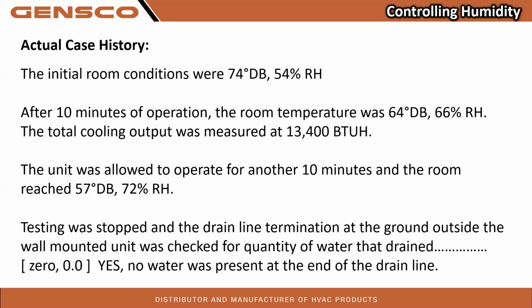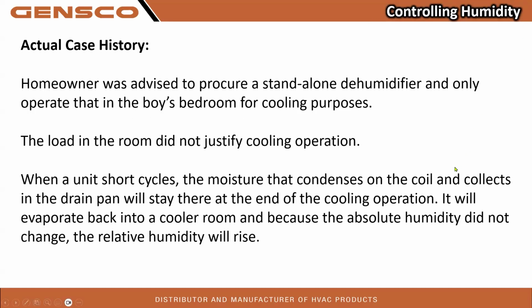This is real. I've run into this. This is probably the worst one I ran into, with a unit being oversized to start with. It never runs long enough to do anything but raise the humidity. I advised this homeowner to never use the unit for cooling. Go to Home Depot, get a standalone dehumidifier, put it in the room, and only operate that. And it must have worked because I never heard back from them.